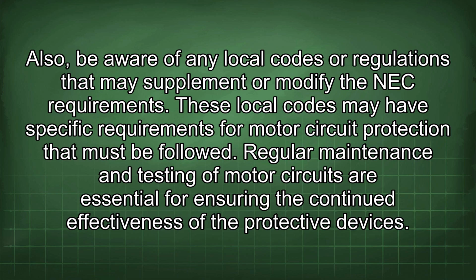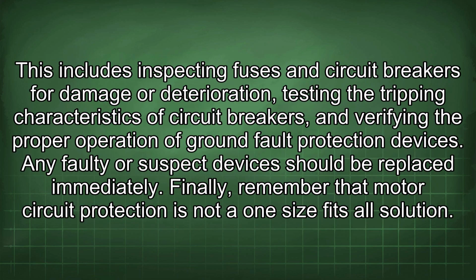Regular maintenance and testing of motor circuits are essential for ensuring the continued effectiveness of the protective devices. This includes inspecting fuses and circuit breakers for damage or deterioration, testing the tripping characteristics of circuit breakers, and verifying the proper operation of ground fault protection devices. Any faulty or suspect devices should be replaced immediately.